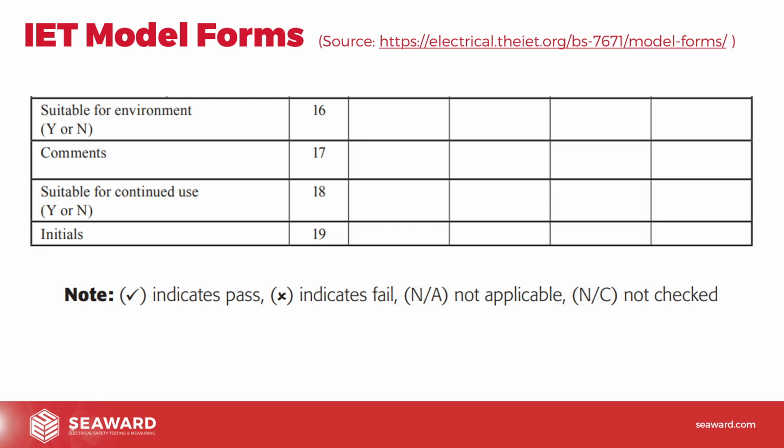So we're letting the duty holder know that we didn't check it, and then probably further down in the comments, we might put no exposed metal parts. So again, we're confirming why we didn't check it. So just be careful on that when you are filling these things in. Just make sure you use the right conventions on there, because sometimes people, when it's a pass, they write pass instead of a tick, or they'll put a tick instead of a yes, or they'll put a not checked instead of a not applicable, or a not applicable instead of a not checked, or those sort of things.